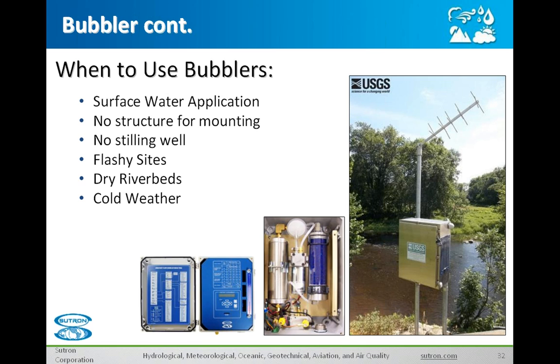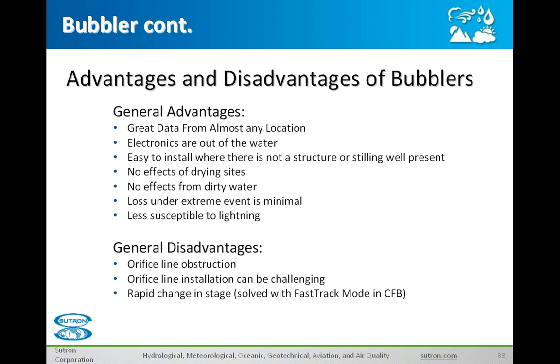We've talked about cold weather and icy conditions — a bubbler works pretty well in those conditions as well, though probably nothing is perfect for iced-over sites. At least with a bubbler you can get underneath the ice and get a good measurement underneath that ice surface when the water is still liquid underneath. Some general advantages of bubblers: they're very accurate from almost any location — almost all of those different types of sites we talked about, a bubbler looks great for virtually all of them. Electronics are out of the water — as Paul mentioned, when you put a pressure transducer in the water you're risking its life. Keeping the electronics out of the water means your bubbler's life will be much longer.